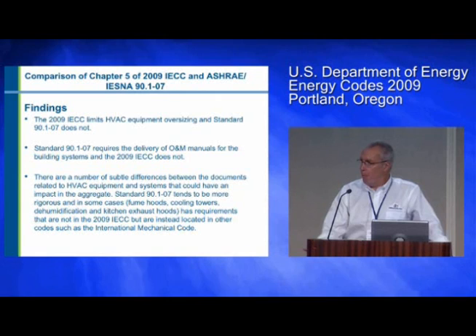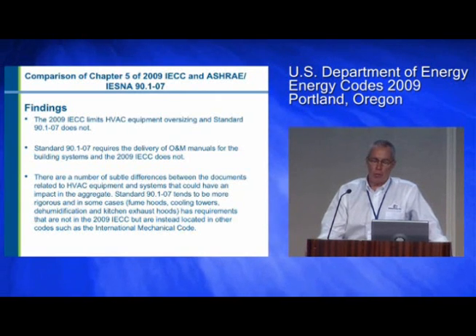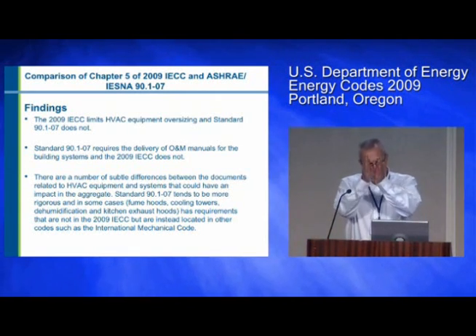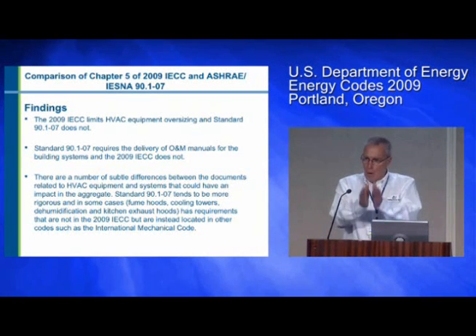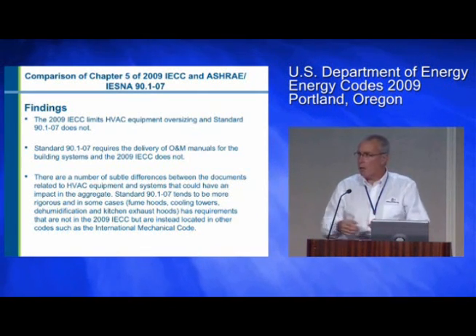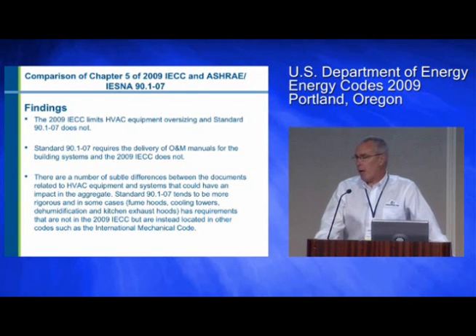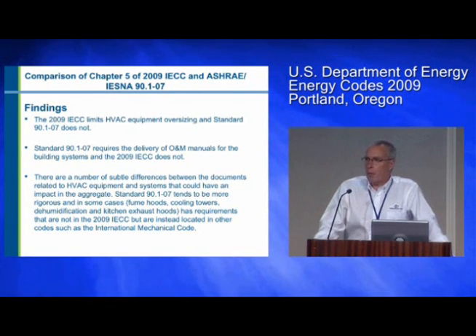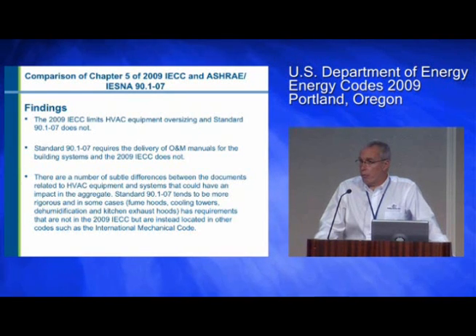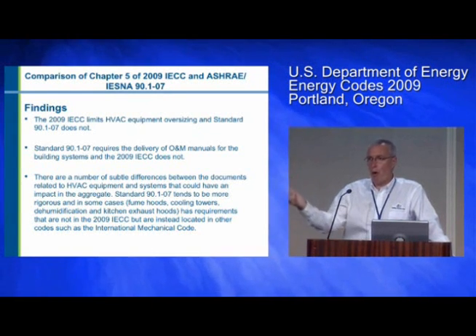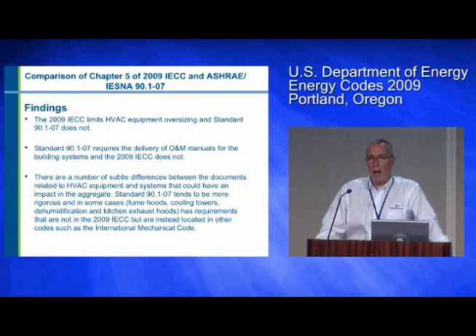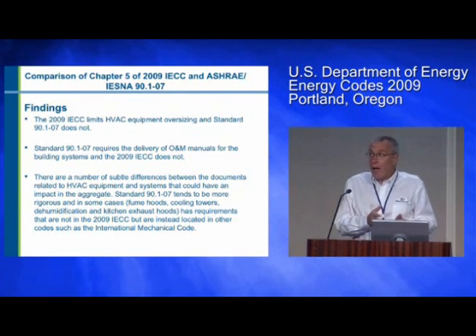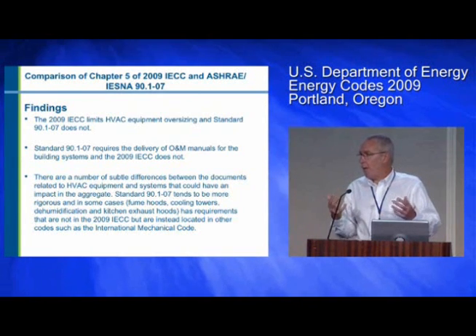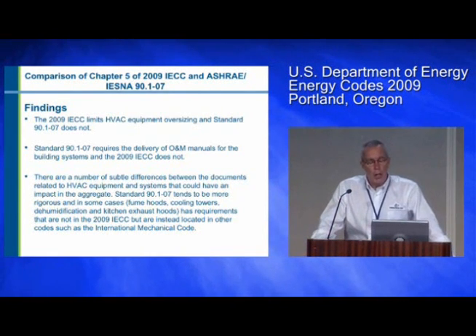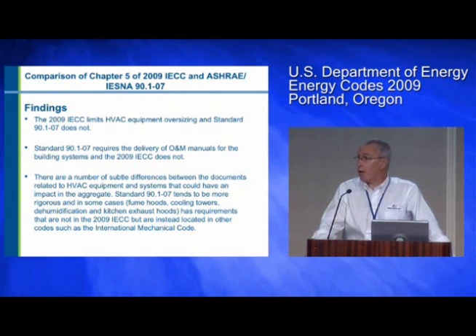But you have to understand, as I think was covered this morning, ASHRAE 90.1 is a standard. It's a design standard. You're going to do the energy thing, you pick up the standard. The IECC has an energy focus, but it's one of 14 codes. And it's intended to be used as part of a package, a building regulatory package. So I might not find something on fume hoods or lab hoods or kitchen exhaust in the IECC, but I'd probably find it in Chapter 5 of the International Mechanical Code.